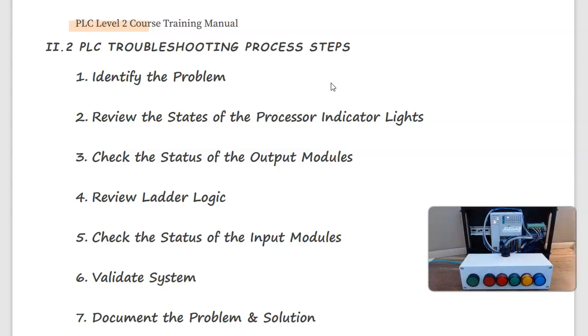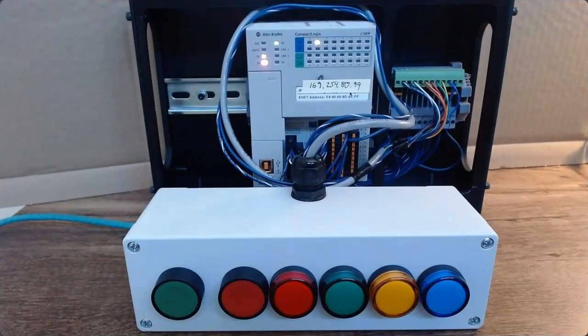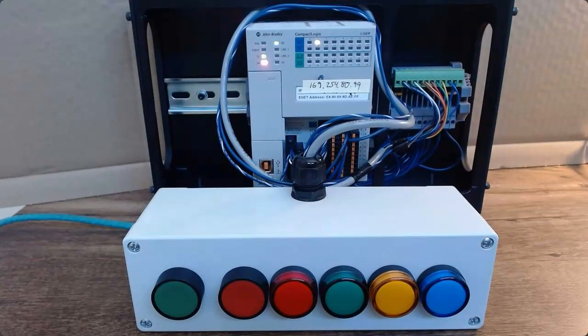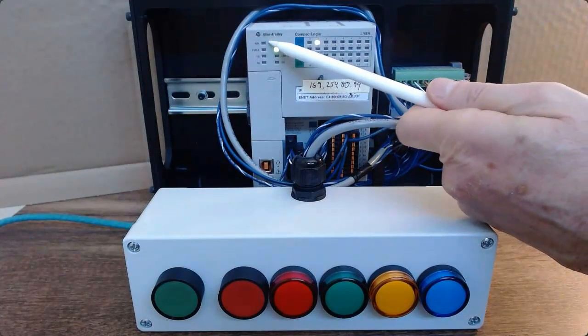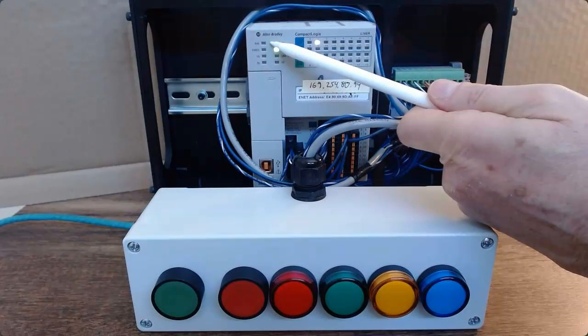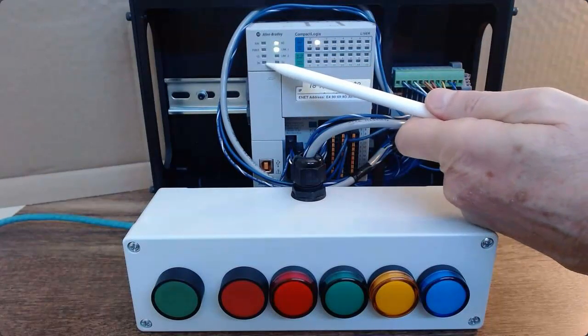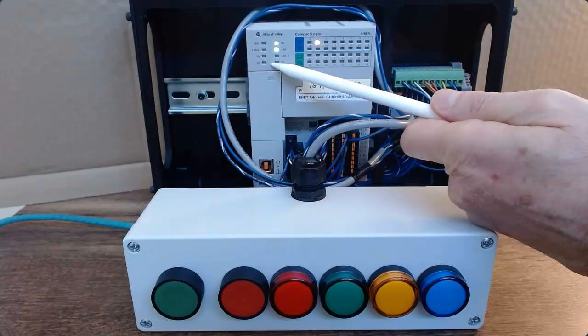Our first step once we understand the problem: we want to review the states of the processor indicator lights. If I take a look at the PLC a little closer, I see a couple things. Number one, the run light is not on, and I also have a flashing OK light which is flashing red, which is my fault light.